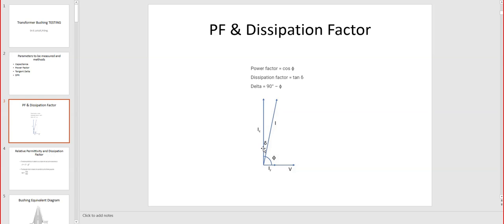The complementary angle of this, what is missing to 90 degrees, is the delta, another Greek letter, the smaller angle here. For that one, we have the tangent of that angle, the tangent of delta, which will be the resistive current over the capacitive current. Please keep in mind this vectorial representation of the dissipation currents, because this is where we need to refer back when we do measurements.